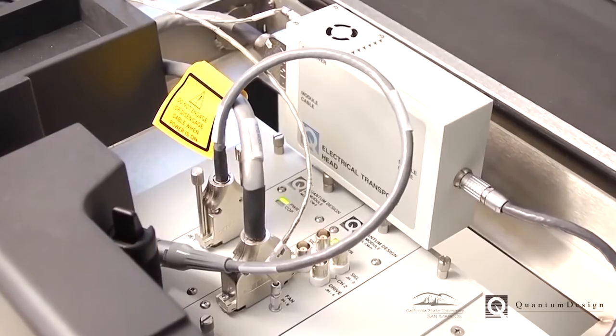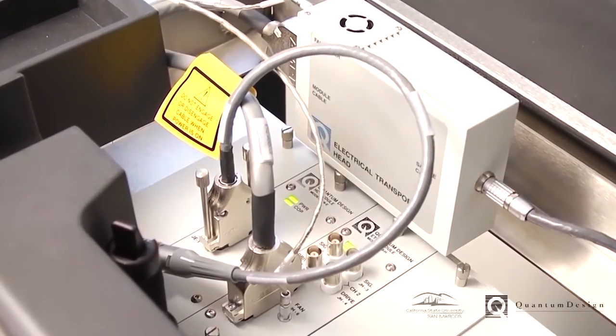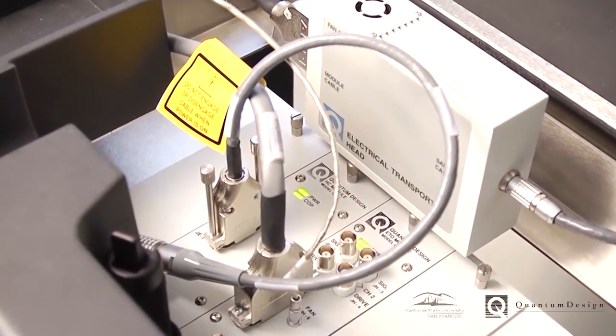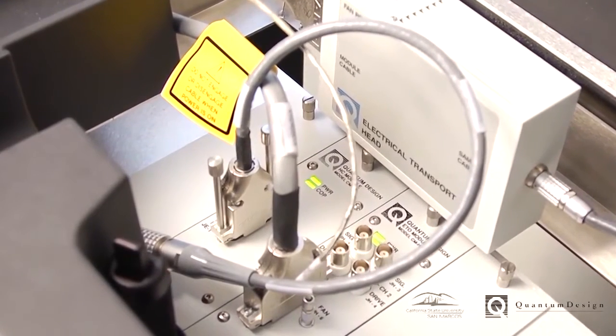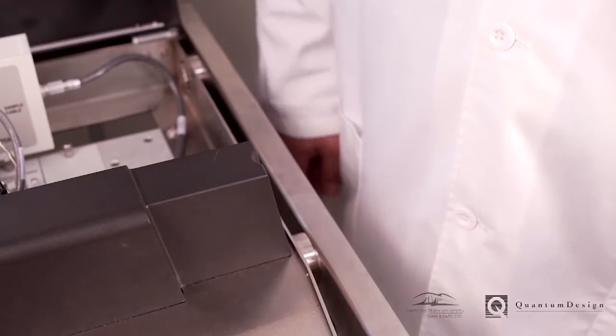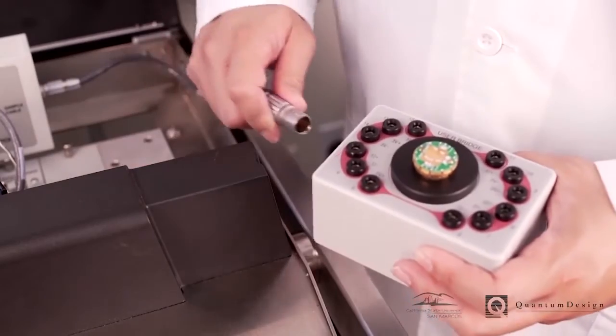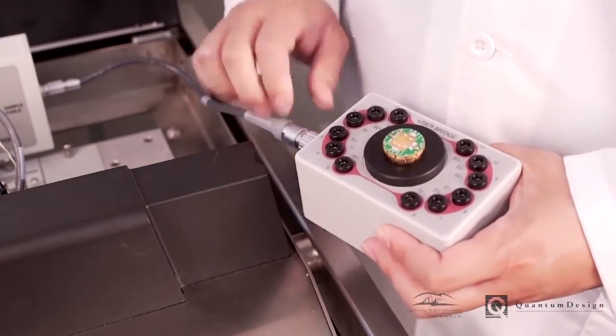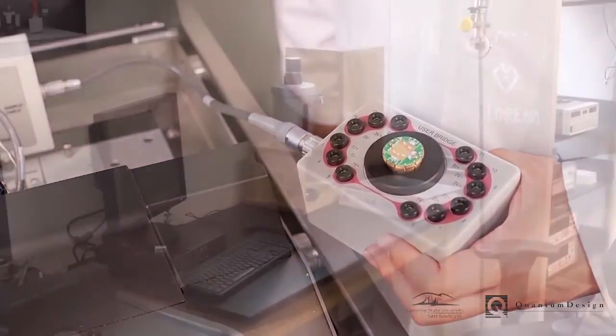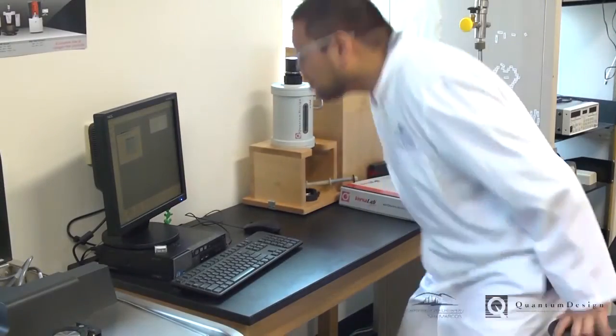The ETO main module should be connected to the module head, which should be connected to the VersaLab interface plug. Never remove the cable between the main module and the module head while the system is powered up, as this can damage the ETO. However, the interface cable to the VersaLab may be removed while the system is on, which is useful for situations when you want to plug directly into the puck box for diagnostic purposes or room temperature measurements.